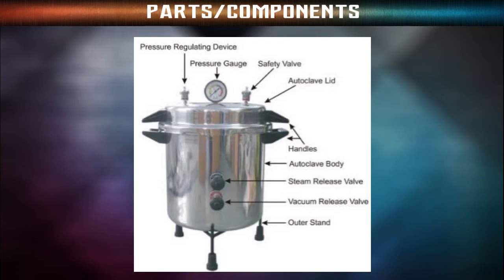The level of water present in the inner chamber is vital. If the water is not sufficient, there are chances of the burning of the heating system. Similarly, if the water is more than necessary, it might interfere with the trays and other components present inside the chamber. Next is the vacuum generator. In some types of autoclave, a separate vacuum generator is present which pulls out the air from the inside of the chamber to create a vacuum inside the chamber. The presence of some air pockets inside the chamber might support the growth of different microorganisms. This is why the vacuum chamber is an important component of an autoclave.